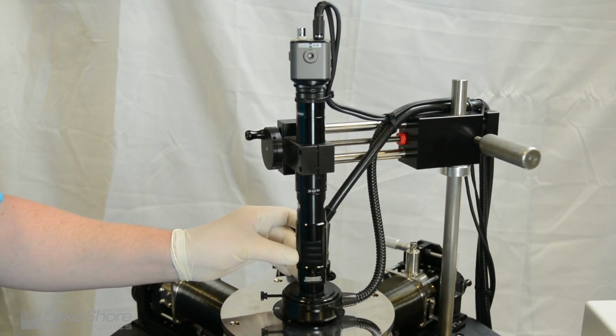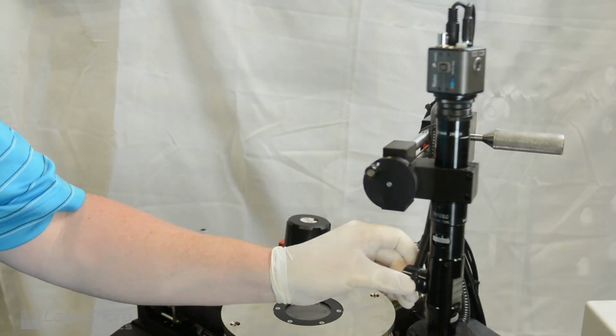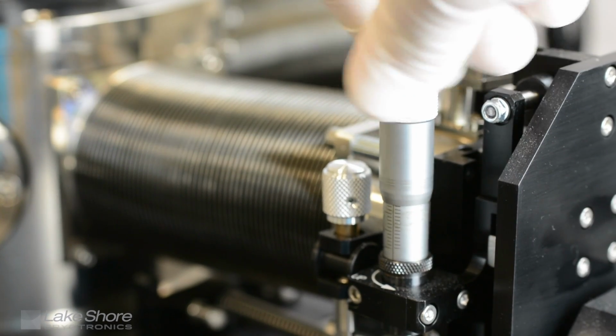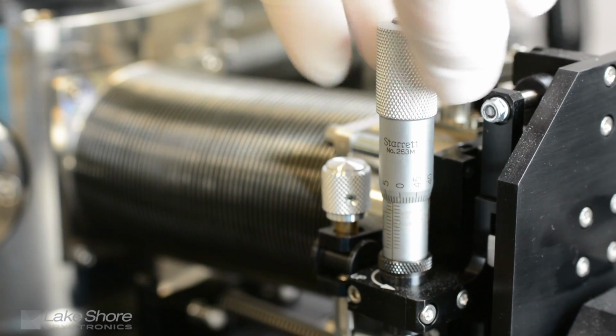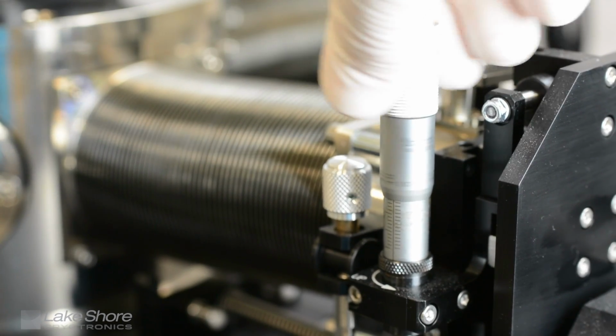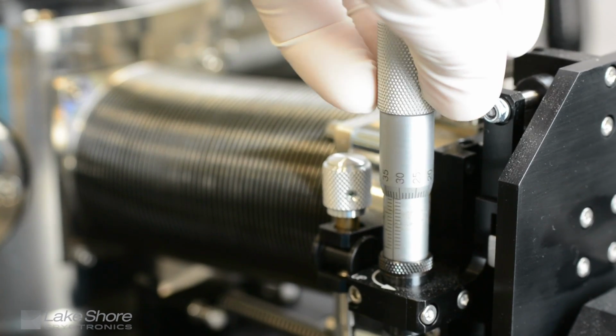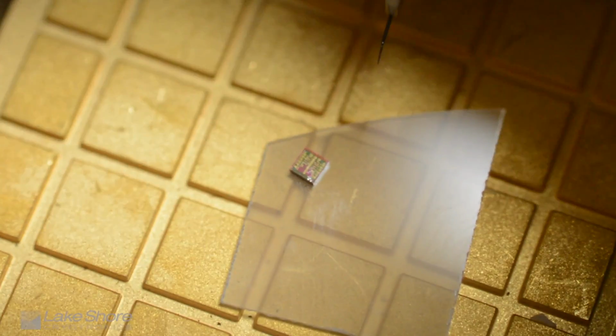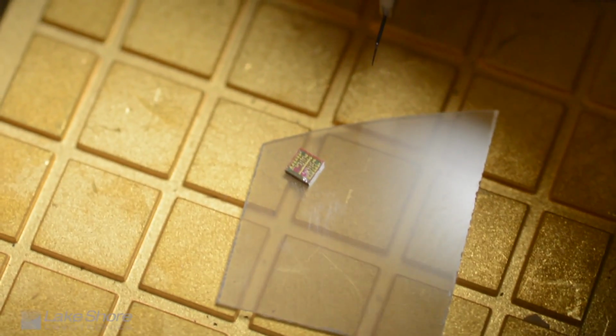In step one, we will ensure the probe is visible through the viewport on the vacuum chamber, and then use the Z-axis micrometer to raise all probes above the sample stage enough to clear the sample landing pad. While visually observing through the vacuum chamber viewport, use the X-axis hand dial and Y-axis micrometers to position the probe tips over the sample landing pad.